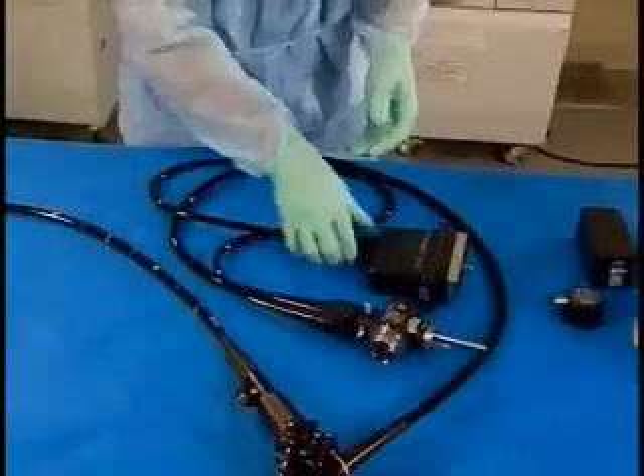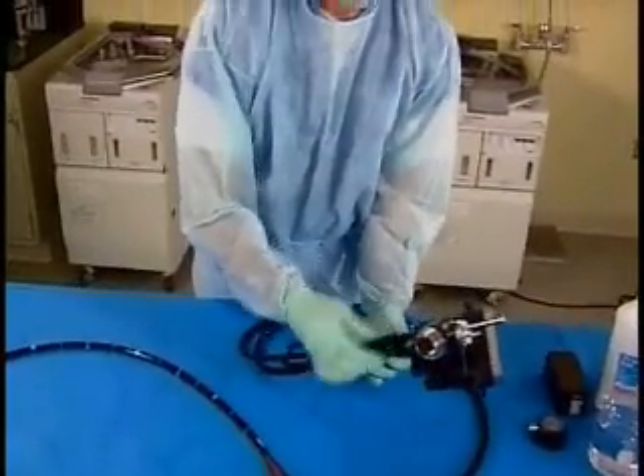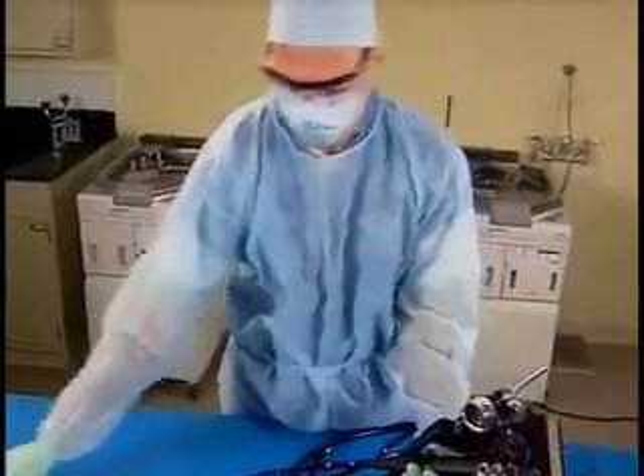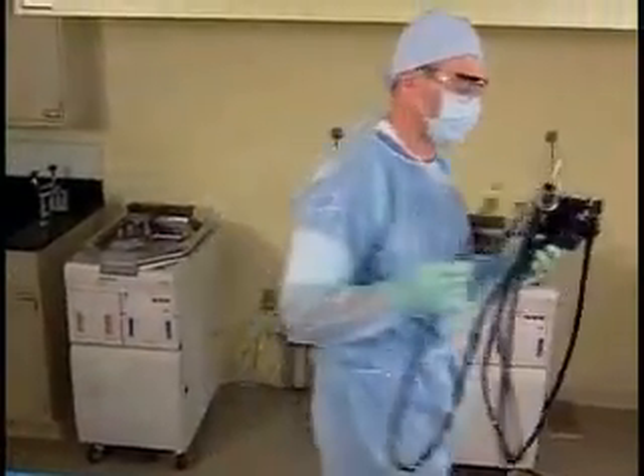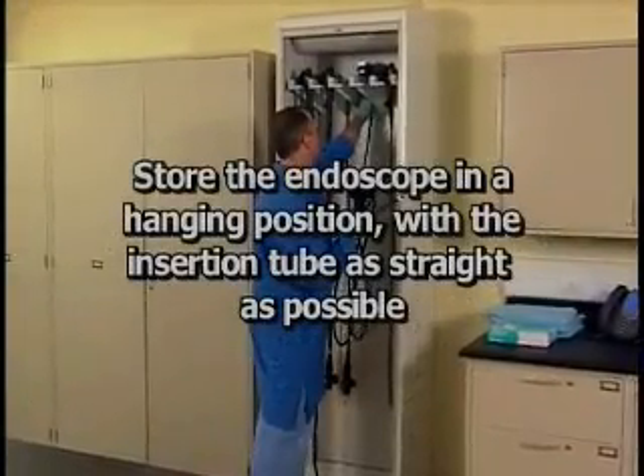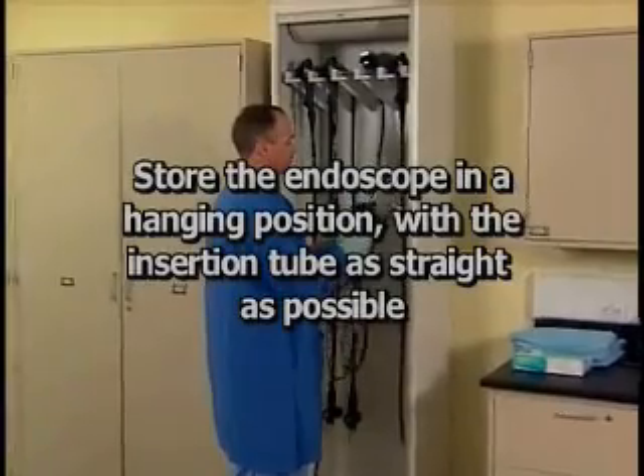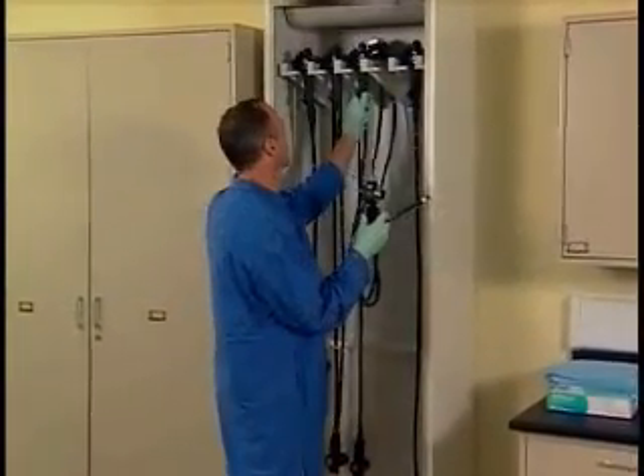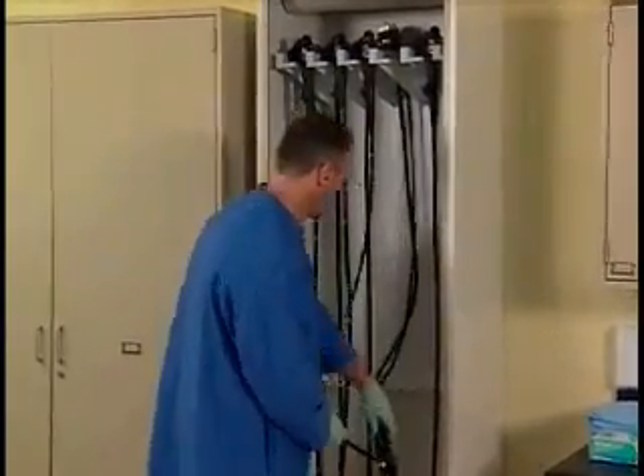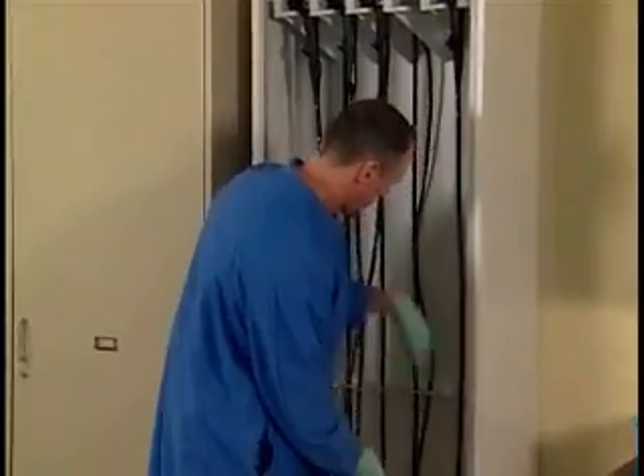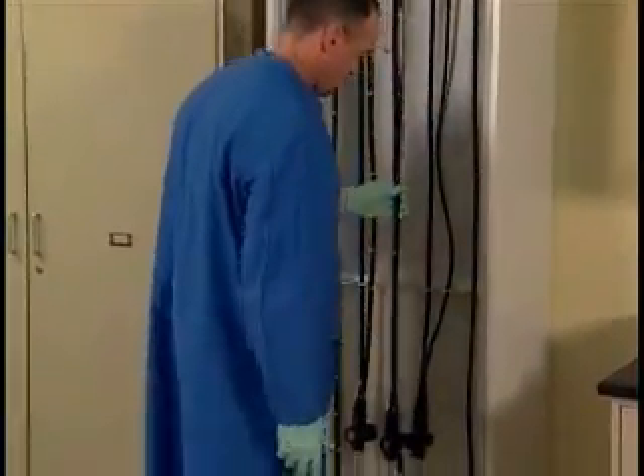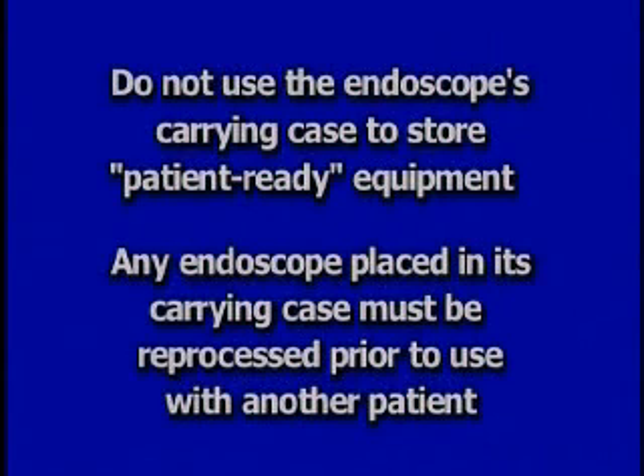Now, hang the ultrasound endoscope in a storage cabinet. The distal tip should hang freely, with the insertion tube as straight as possible and avoiding contact with other instruments. A word of caution: do not use the endoscope's carrying case to store patient-ready equipment. Any endoscope placed in its carrying case must be reprocessed prior to use with another patient.